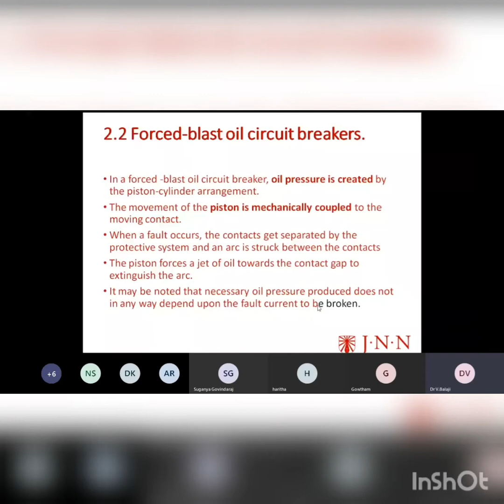Then next point, it may be noted that the necessary oil pressure produced does not in any way depend upon the fault current. That's why I told it, because an external source is there to send that pressure of oil. It does not depend upon the current, which actually does in the case of your self-balanced oil circuit breaker. So next we will see on to that. I hope that everybody, it is audible and clear.